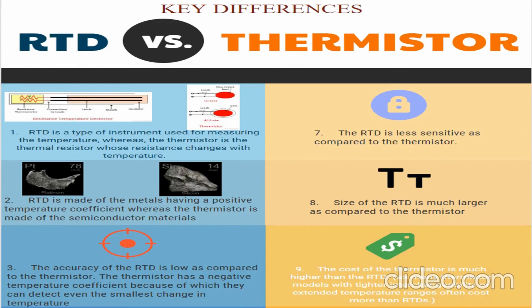Next, RTD is made of metals having a positive temperature coefficient, for example, platinum and nickel, while thermistor is made of semiconductor materials, for example, silicon. Comparing accuracy, the accuracy of RTD is lower compared to thermistor. This is because, as we have learned previously, thermistor has a negative temperature coefficient and is able to detect even the smallest change in temperature. RTD is less sensitive than thermistor. RTD is large as compared to thermistor.